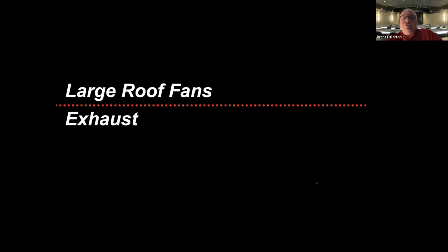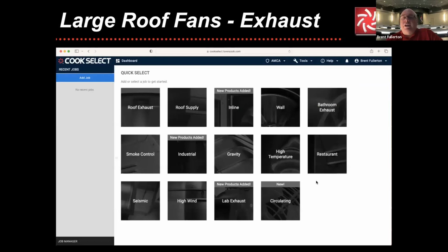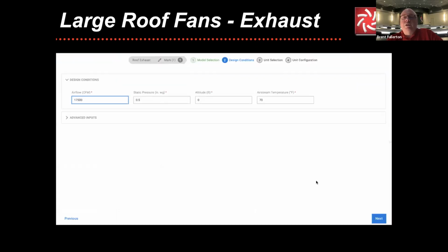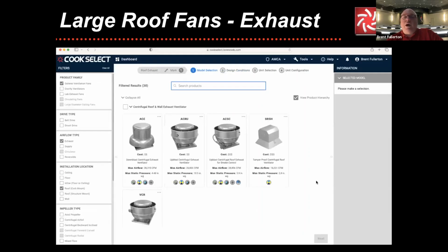So let's dive into large roof fans and specifically the exhaust types. With our online software, you can go in and make a lot of selections right there. In the upper left-hand corner, roof exhaust is number one. You can input your CFM and static pressure. In this case, I've done 17.5 at a half an inch, because that seems to be a very often go-to range depending upon the size of the building that you might have. So you can get a wide range of products that come up.